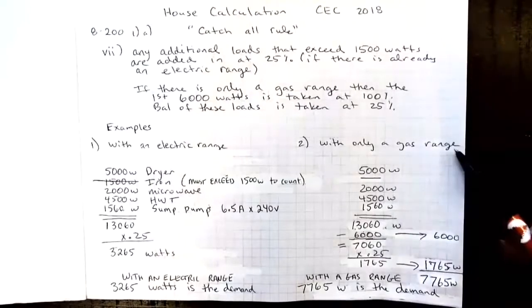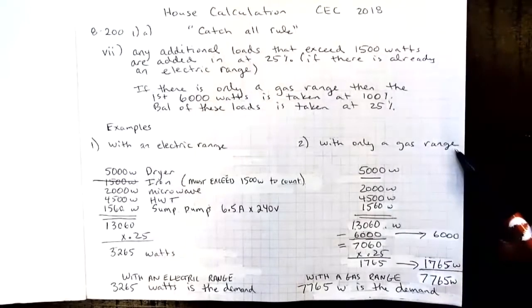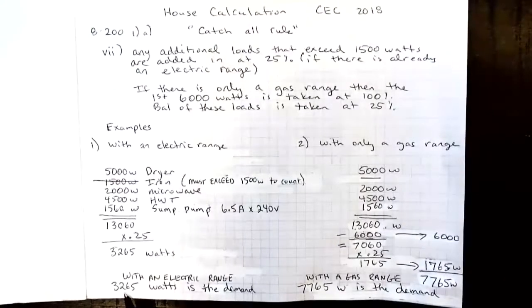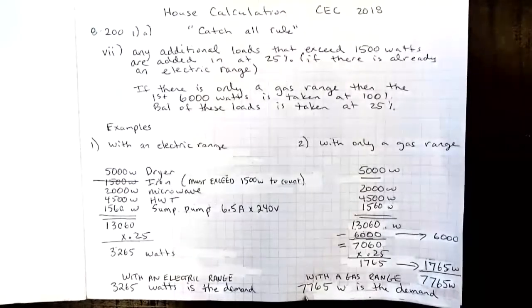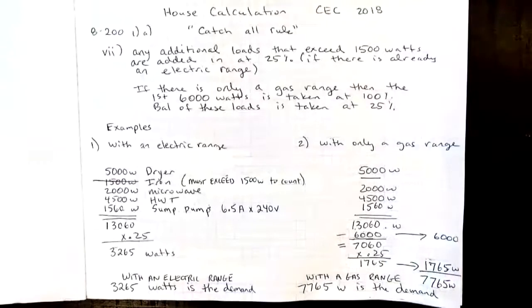These two numbers now add up to the total demand that we would apply for the items in the catch-all rule when there is only a gas range in our home. Notice that when we have an electric range, those items would cause a demand of 3,265, but when we only have a gas range, the demand is 7,765, substantially more.